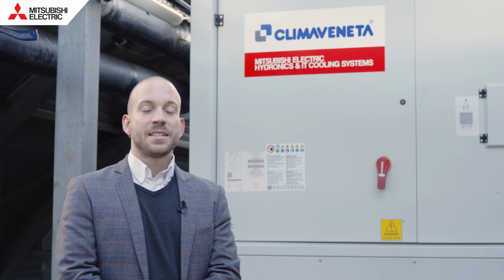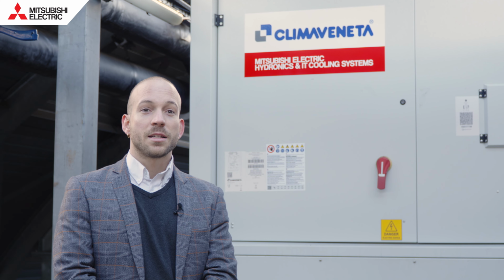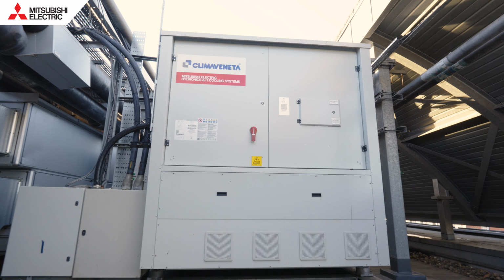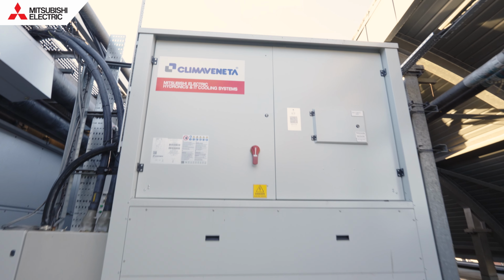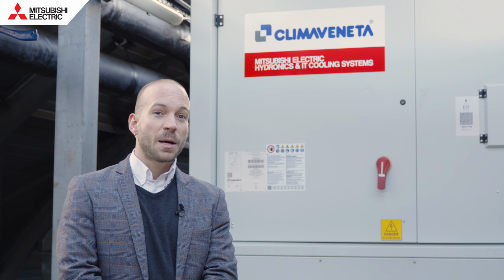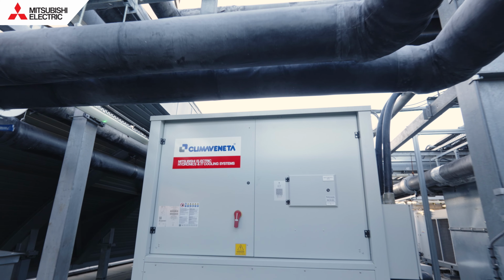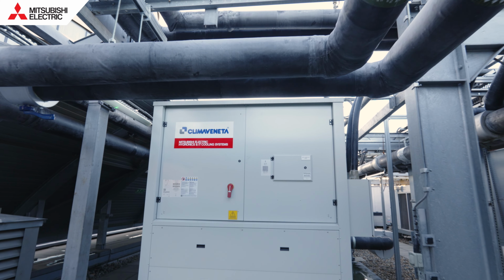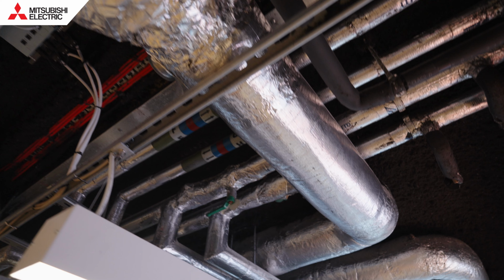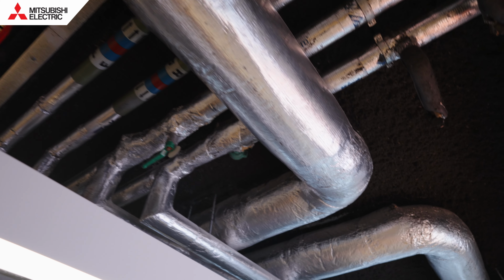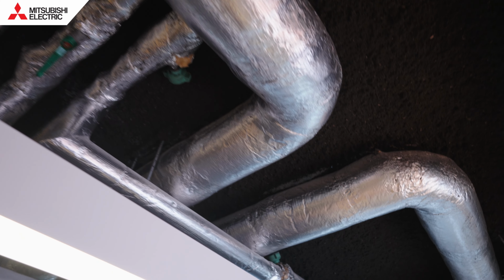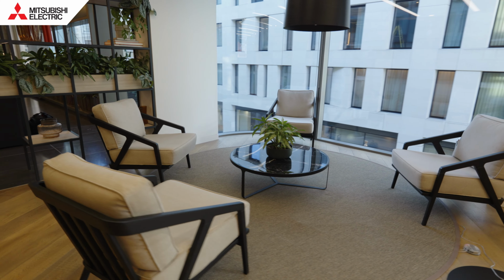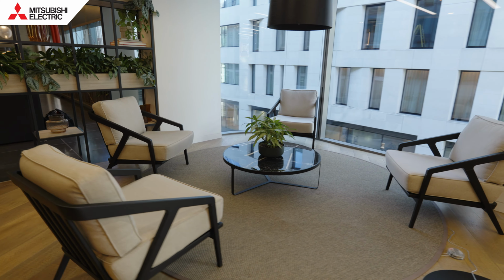Initially, the building was heated by 4 atmospheric boilers equating to over 1 megawatt of heating capacity. The new equipment comprises 2 heat pump chillers with a combined heating capacity of 1100 kilowatts and a combined cooling capacity of 1200 kilowatts. The benefit of using the Mitsubishi 4-pipe heat pump chillers is that there's a year-long cooling load and we get to use some of the waste heat from that process to heat the building.